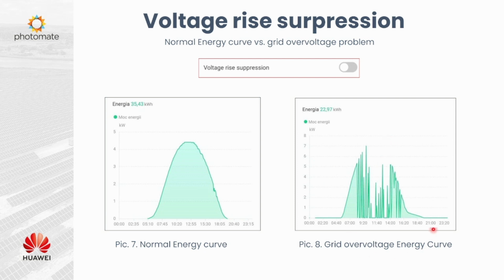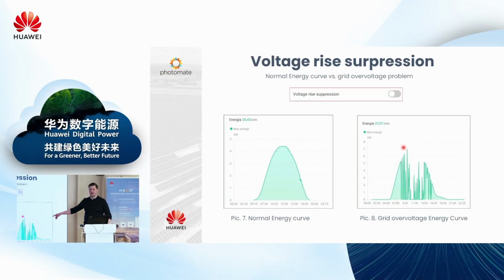This is how the PV system performance usually looks when you have a grid over-voltage problem. The inverter is shutting down because it crossed the level of the allowed voltage on the grid, and it's trying to start up, and the whole process repeats for almost the whole day. You can estimate on your own how much power has been lost here.